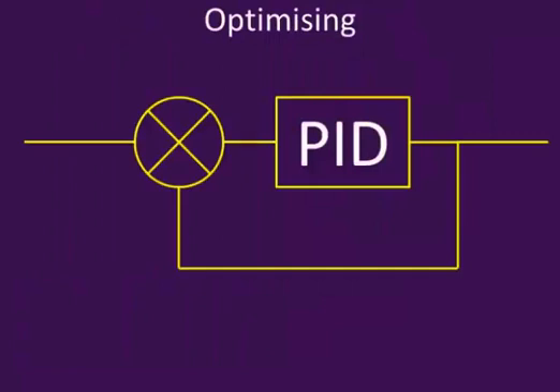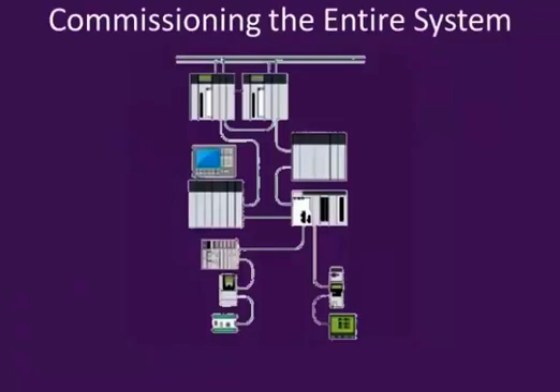Next stage is optimizing stuff. Perhaps we've got some control loops that need tuning. We might have some PID tuning to do. We deal with that in another course. Having commissioned the individual PLCs, the components, we now need to check the network and interconnections. There may be variables that need to be passed from one PLC to another.